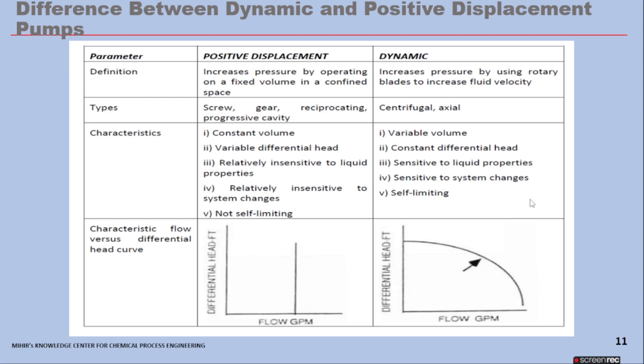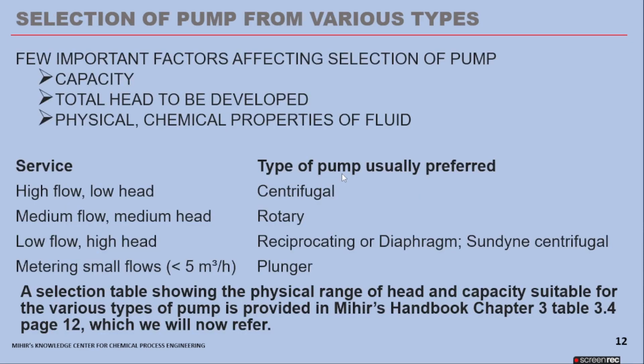The major salient points to note are: PD pumps are constant volume; centrifugal pumps are constant head. PD pumps are relatively insensitive to liquid properties, whereas centrifugal pumps are sensitive to liquid properties.